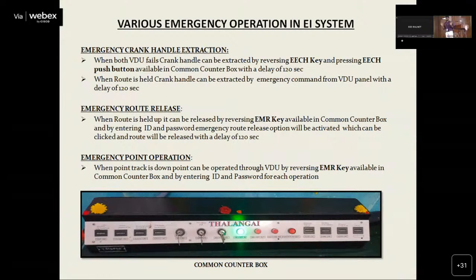When a route is locked, we can normally give the command for crank handle extraction from the VDU itself. But once the video fails, we use this extreme emergency crank handle key and button. Similarly, for emergency route release, we reverse that key, and the command with ID and password can be given from the panel to release the route. For emergency point operation, the same process applies: we reverse the emergency key, and the command with ID and password can be given from the panel to operate the point.